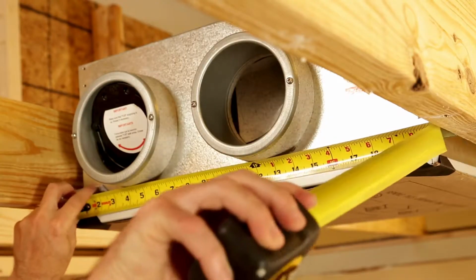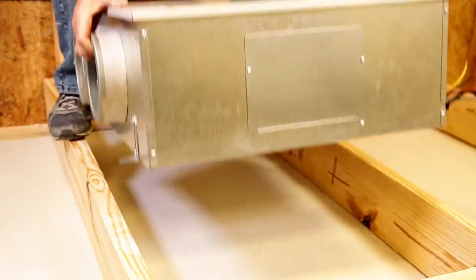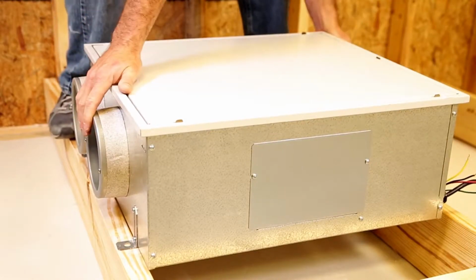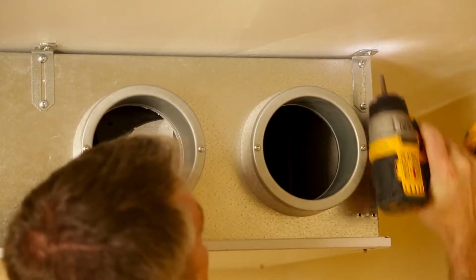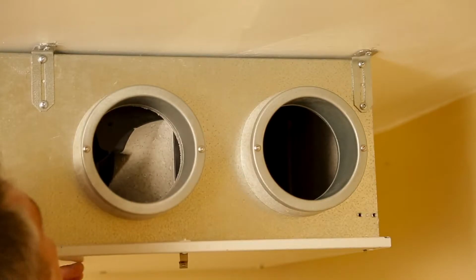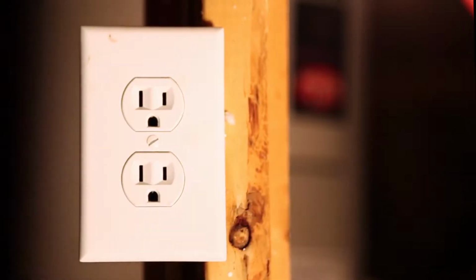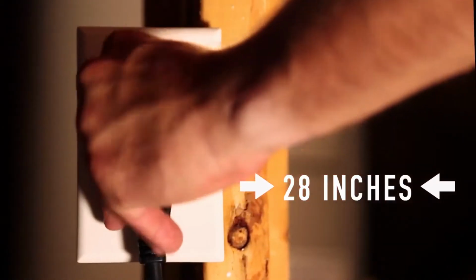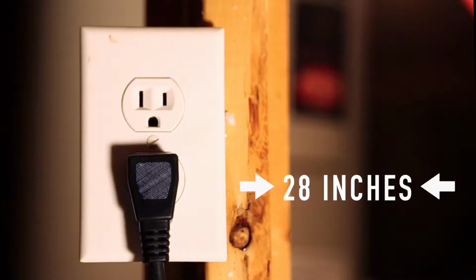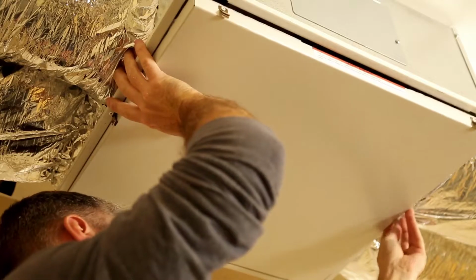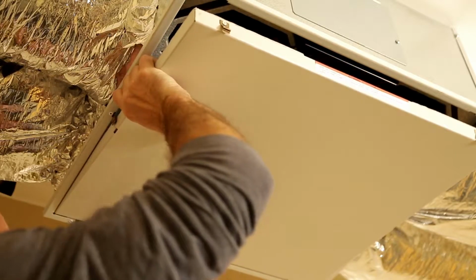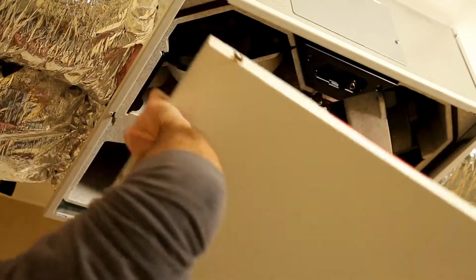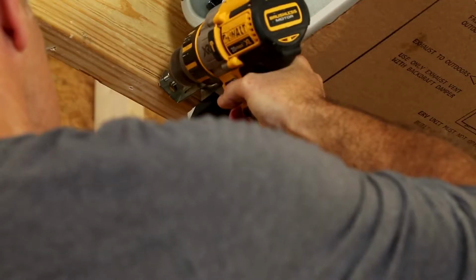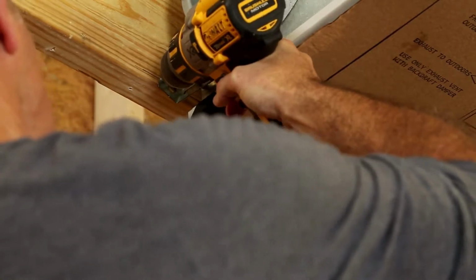The ERVS100 can be mounted in the ceiling, in an attic, or in a small closet or mechanical room. Regardless of where the ERVS100 is installed, there must be a standard 3-prong electrical outlet within 28 inches of the unit that must be connected to its own dedicated circuit. You will also want to leave at least a 12-inch clearance for the door, core, and filters to be removed for maintenance. The installation is fast and easy in new construction.